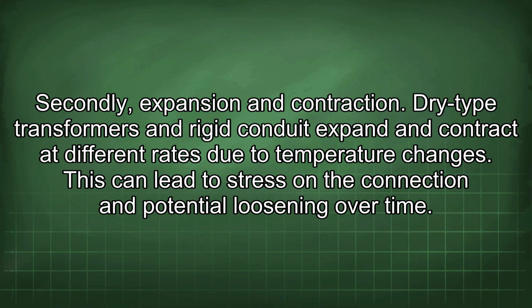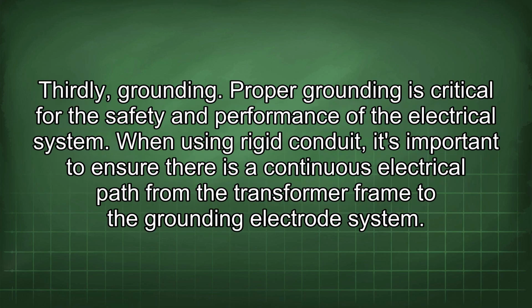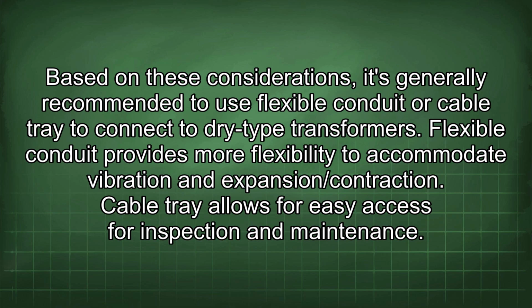Secondly, expansion and contraction. Dry-type transformers and rigid conduit expand and contract at different rates due to temperature changes. This can lead to stress on the connection and potential loosening over time. Thirdly, grounding. Proper grounding is critical for the safety and performance of the electrical system. When using rigid conduit, it's important to ensure there is a continuous electrical path from the transformer frame to the grounding electrode system.